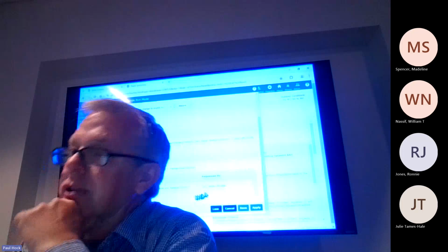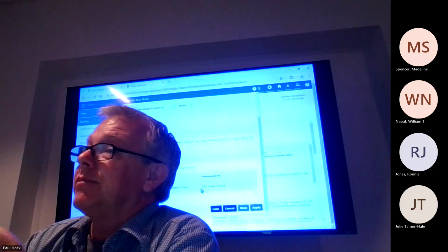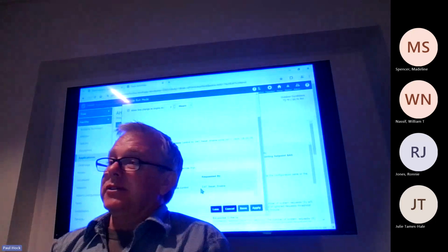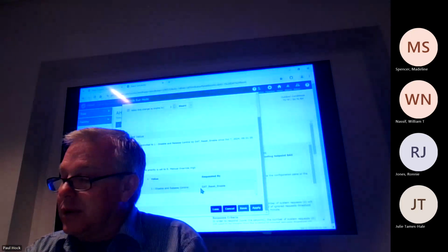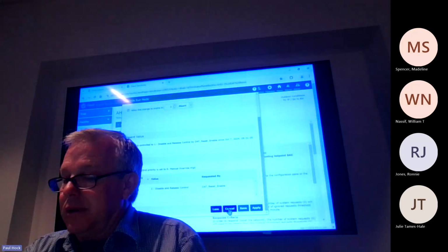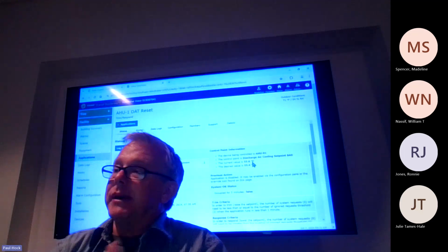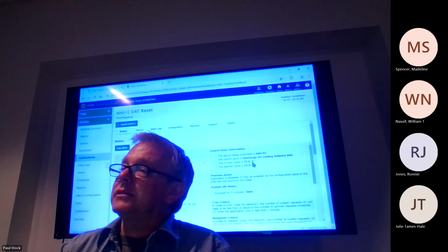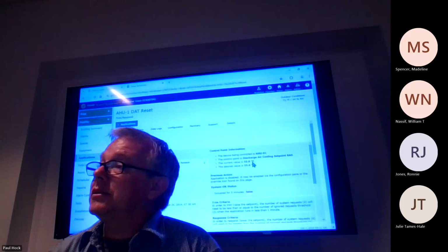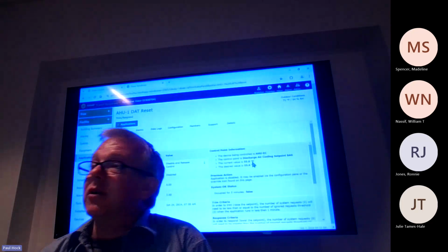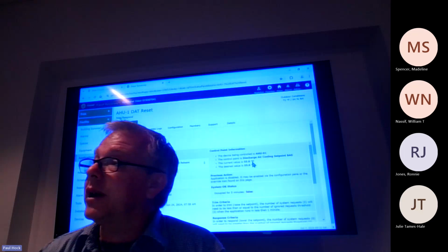Put a discharge air temperature reset in there, just in case. The sequence didn't call for it, but I put one in there just in case you guys need to enable it. What this does is it looks at all your space temperatures, and it will start resetting the discharge air temperature on the air handler based on the building temps. It is disabled right now, so if the winter months hit and we need to do that, let us know, and I'll show you where to do that.